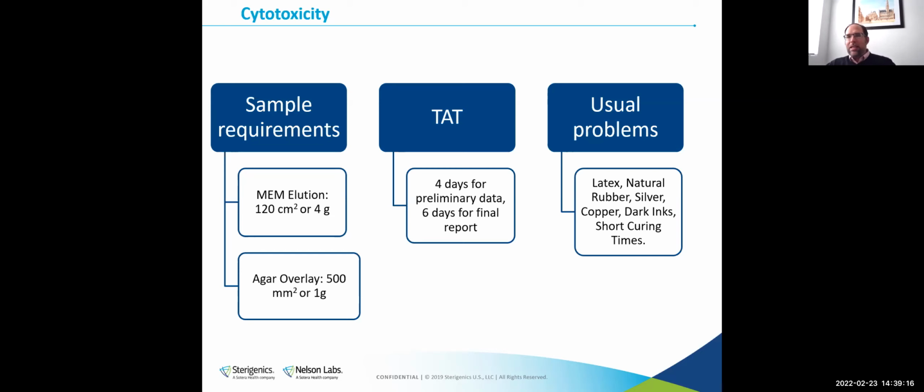So if you have an adhesive that isn't cured all the way, even though the adhesive is probably safe if it's cured, if it's not cured all the way, we're probably going to see issues. That's the same for colorants, things like that. So just keep those in mind. Those are things we do see issues with cytotox. So we always call cytotox your best friend and worst enemy because it's the cheapest, quickest screening, but it's also the one that fails the most often.